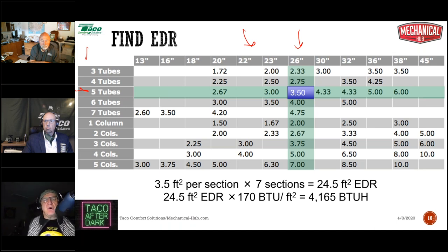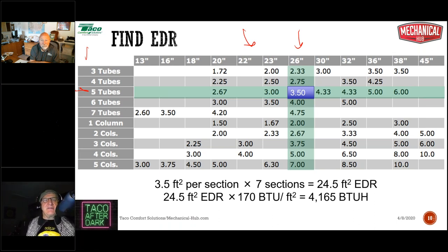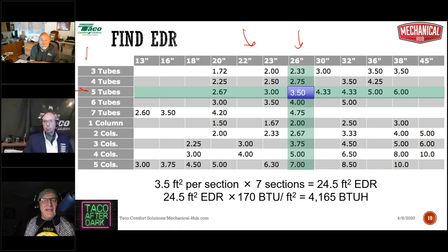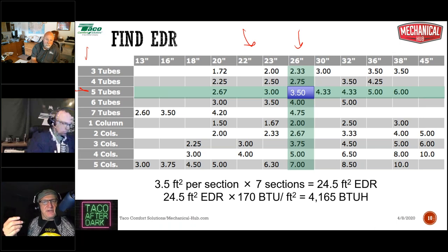If you've ever looked at some old boiler output charts, they'll have the DOE output, they'll have the net IBR output, and then they'll have the square feet of radiation number, and it's given to you in square feet. Well, it's square feet of EDR. Just take that number, multiply it by 170, and you'll get the potential output of the boiler. It's a leftover from steam days.